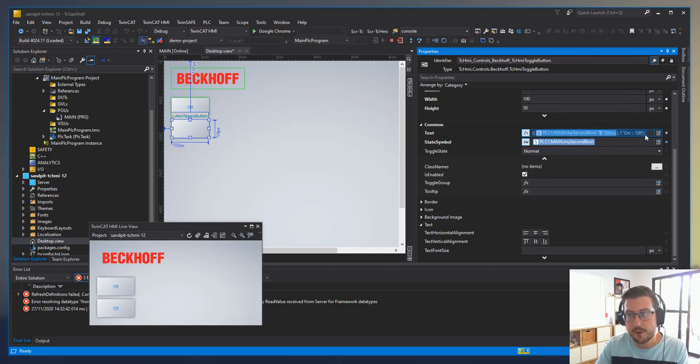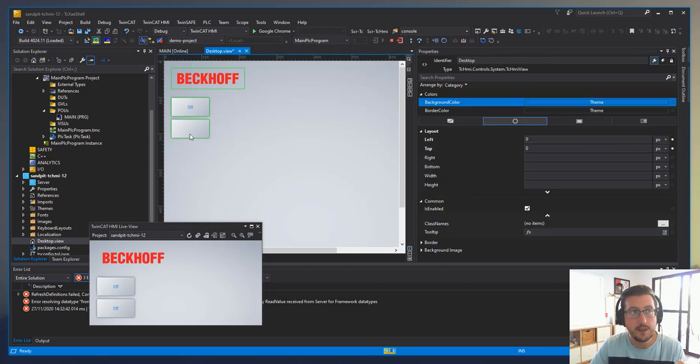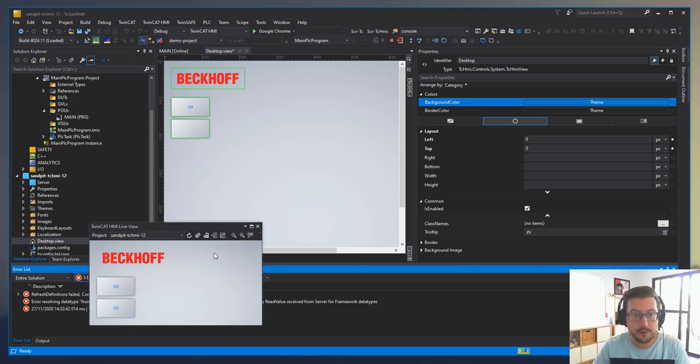But inside the text field, we can write a certain amount of JavaScript. And JavaScript allows us to do inline if statements. I think they're called ternary ifs or tertiary ifs, that sounds right, which says evaluate this first part. So I'm going to actually evaluate the symbol itself. The question mark says, right, this is the start of the if statement. If the first part evaluates as true, return this. And if it evaluates as false, return this. So there we go. The downside of this is that in design view, before live view, it's not running that JavaScript, so you don't see any text. It's only once you get to the stage where you're live that the JavaScript kicks in.